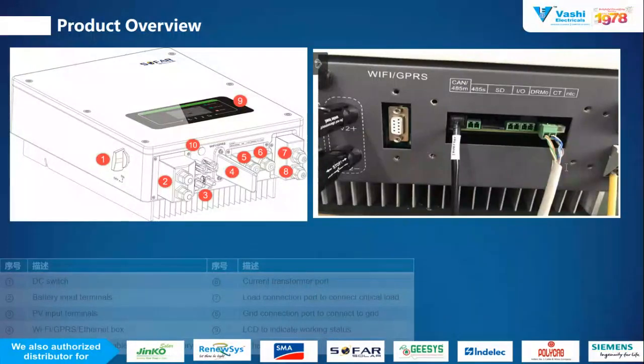This is the image of the hybrid inverter, where you can see the different points 1, 2, 3, 4 according to their connection. First is a DC switch, used for on-off control of the battery and PV connectors at the input side. Fourth is a Wi-Fi, GPRS or Ethernet connection. Fifth is the BMS section, enlarged in the right side image, where there are different connections like CAN connection, RS485 connection, NTC connection. We also have an SD card facility available in the hybrid inverter, as you can see in the right side image. You can easily get the data of the hybrid inverter even if it is not online. Insert your SD card in the laptop or in your mobile, and you can easily get the data in Excel format.